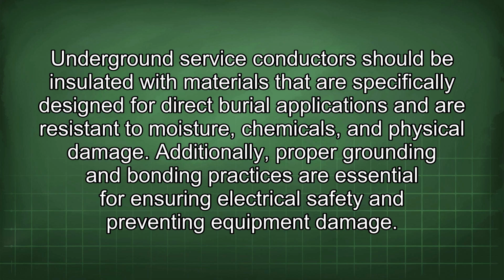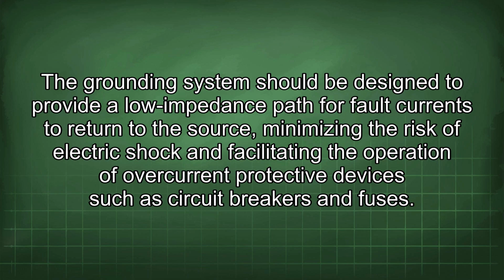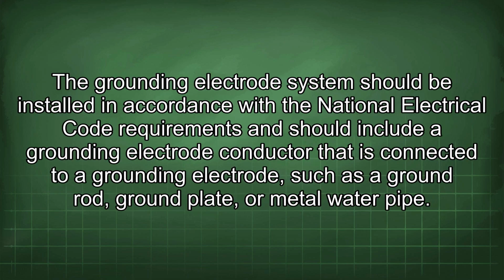Additionally, proper grounding and bonding practices are essential for ensuring electrical safety and preventing equipment damage. The grounding system should be designed to provide a low impedance path for fault currents to return to the source, minimizing the risk of electric shock and facilitating the operation of overcurrent protective devices such as circuit breakers and fuses. The grounding electrode system should be installed in accordance with the National Electrical Code requirements and should include a grounding electrode conductor that is connected to a grounding electrode, such as a ground rod, ground plate, or metal water pipe.